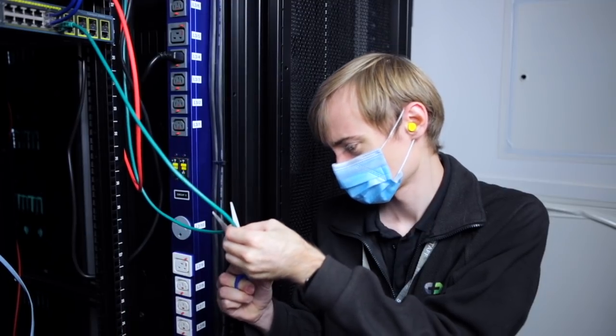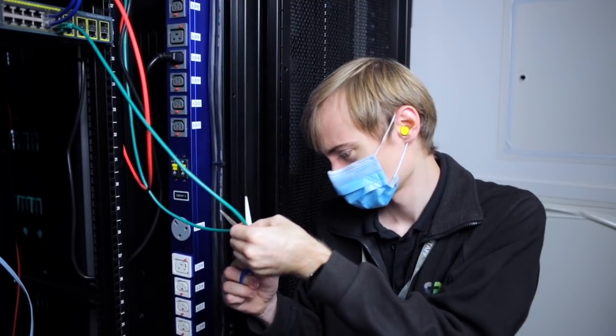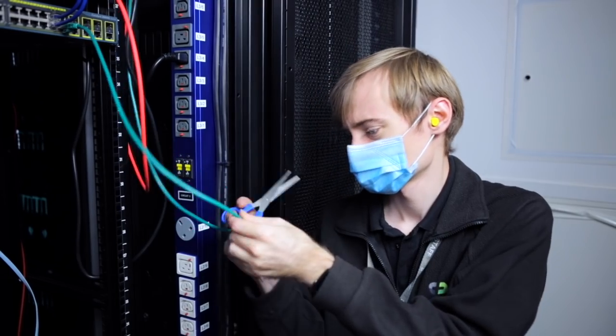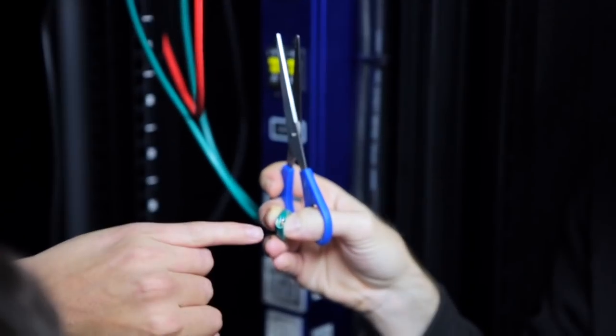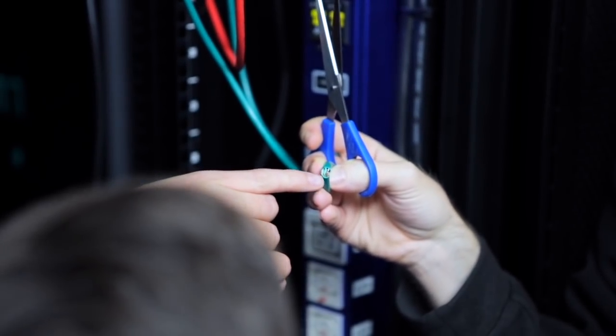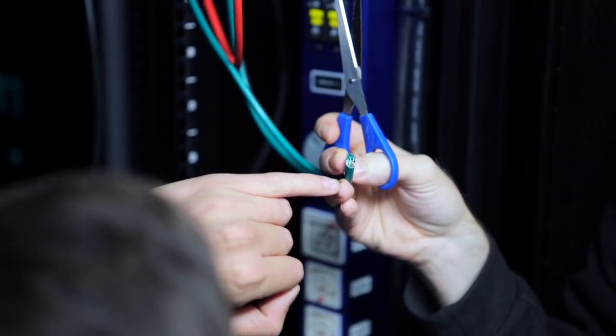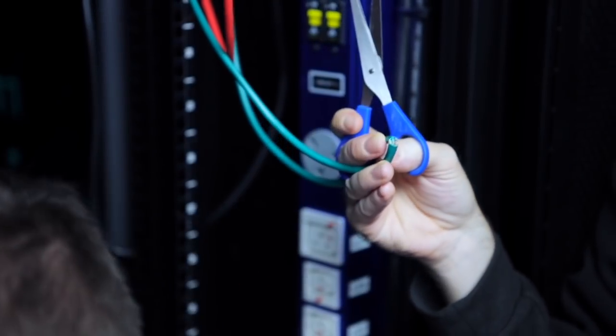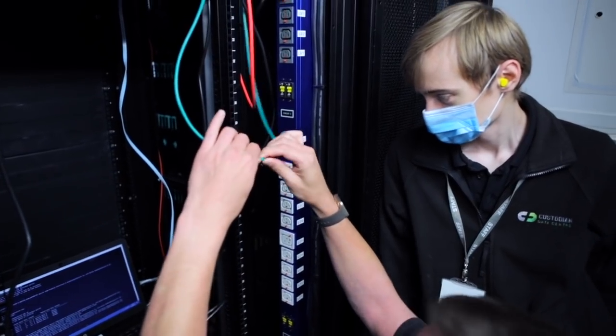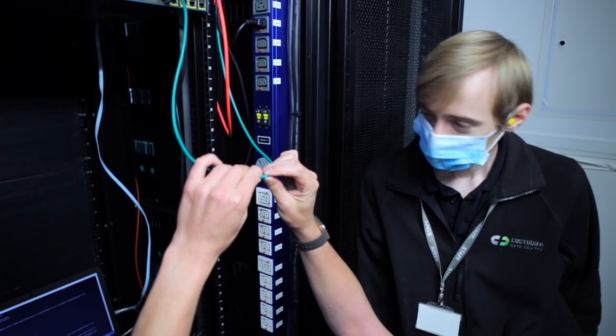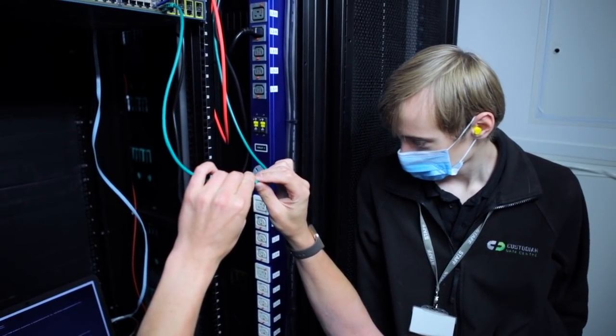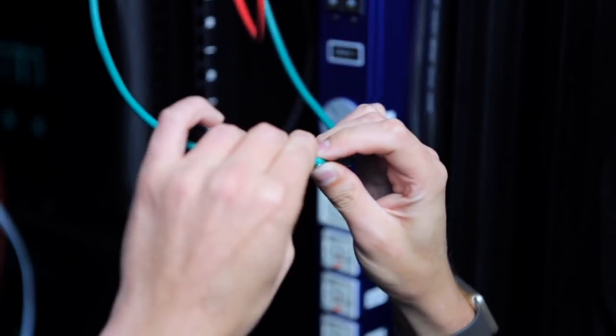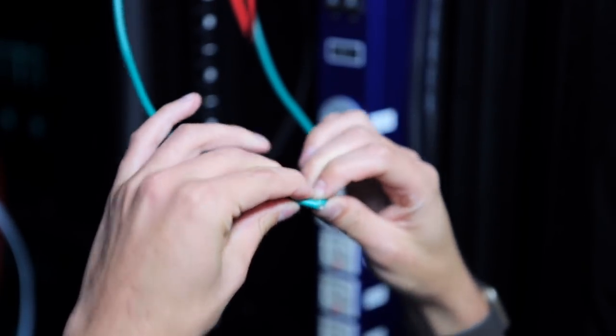It only needs to be cut enough just to get a core that's broken and then the TDR will show it. This cable here, it's actually got two, one core broken, one actually split. So if we just have a little manipulation of the cable, try and touch some of the cores together again, it might do something. Apparently not. But we can now run the TDR again.